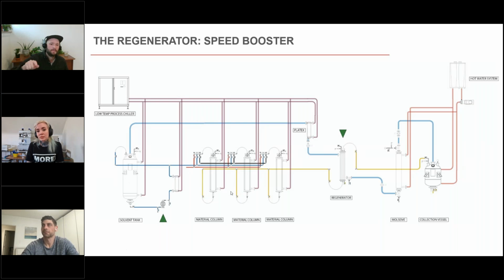And that way, every time you decrease the pressure in the solvent tank, the recovery speeds up. You're dropping the pressure and you're speeding up how fast the butane goes back. And we're using that nitrogen to clear all of the butane out of the column so that you're not leaving any behind and having extra solvent loss.